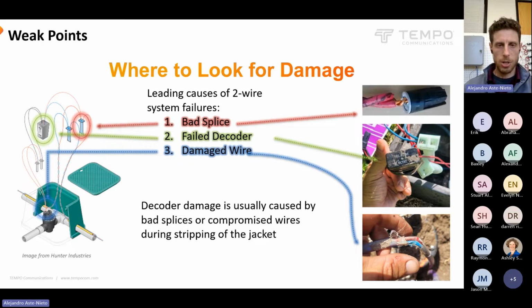And typically a decoder will fail because water is allowed in to the conductors and can be attracted into the electronics of the decoder. Especially these systems that have 2-way communication, there's constant voltage and current going on, that literally attracts water into these exposed crevices. And when you have electricity combined with water, it dramatically accelerates corrosion. These systems where there's constant communication happening are much more susceptible to failure from poor splices.